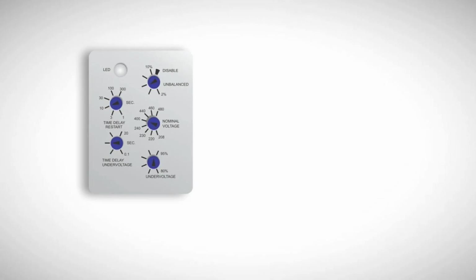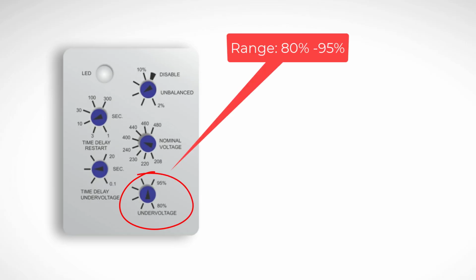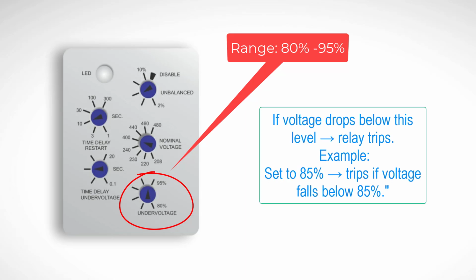This sets the undervoltage threshold. Range 80% to 95% of nominal voltage. If voltage drops below this level, relay trips. Example, set to 85%, trips if voltage falls below 85%.